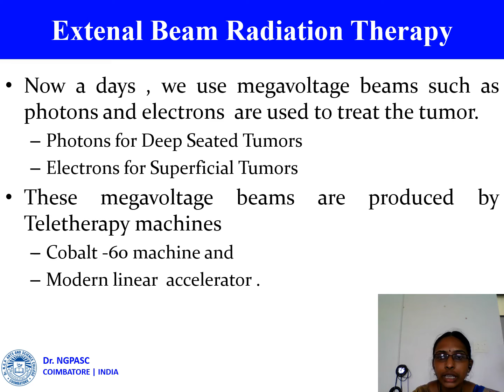This is the picture of a linear accelerator. It consists of a treatment couch, a treatment head and a gantry. During treatment, the patient lies on the couch. The treatment head consists of the X-ray target, flattening filter, scattering foil and beam collimating devices such as the primary collimator, secondary collimator and jaws. The gantry is used to rotate the treatment head all around the patient during treatment.